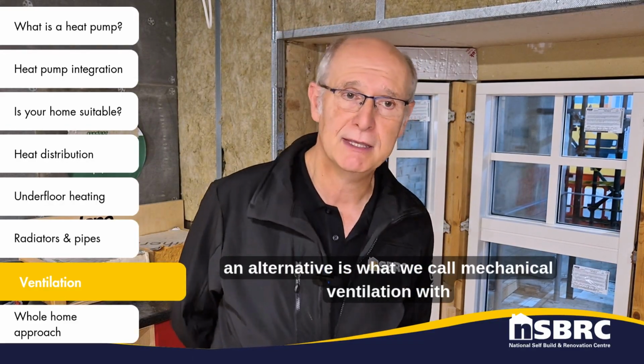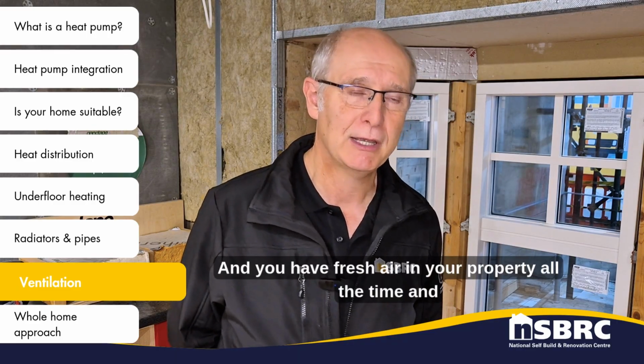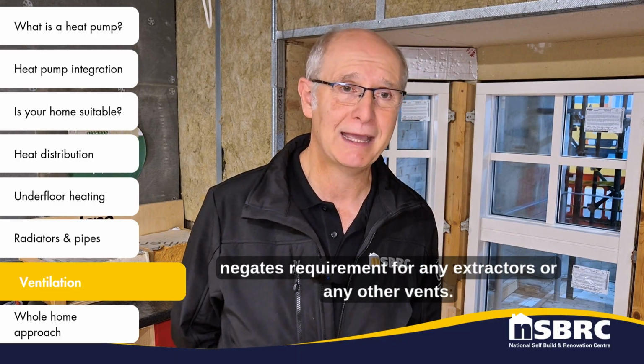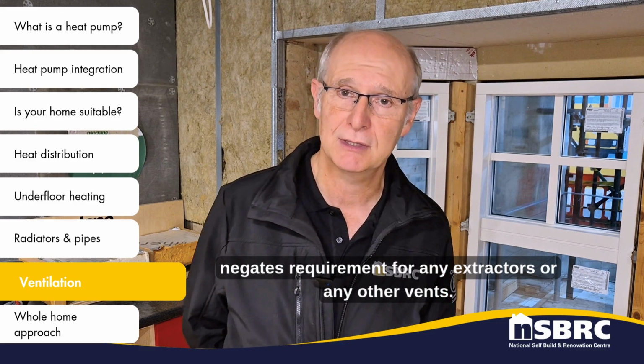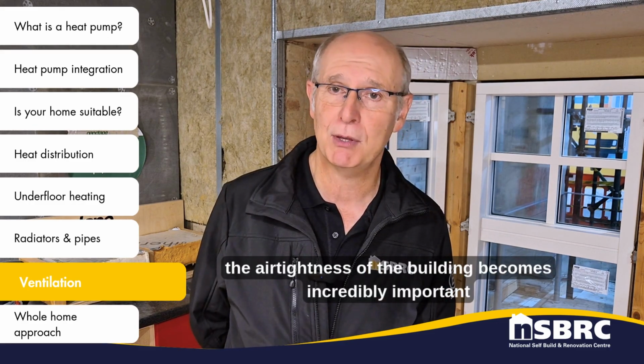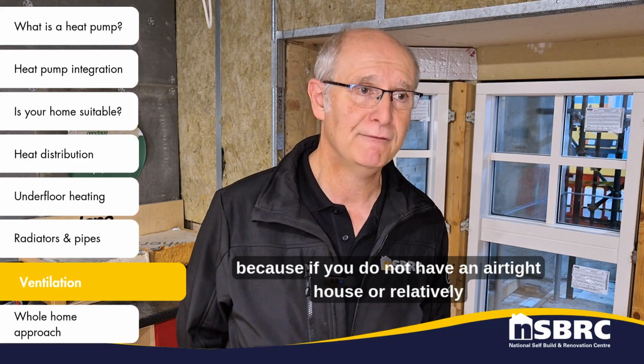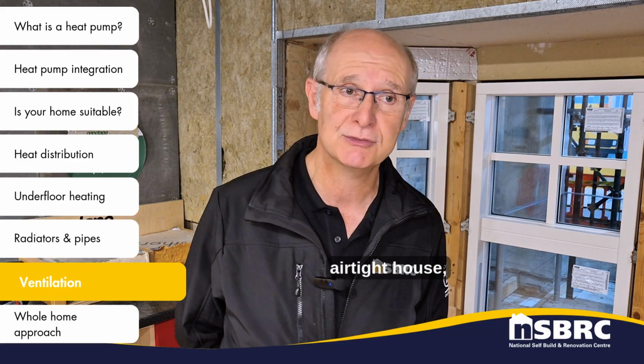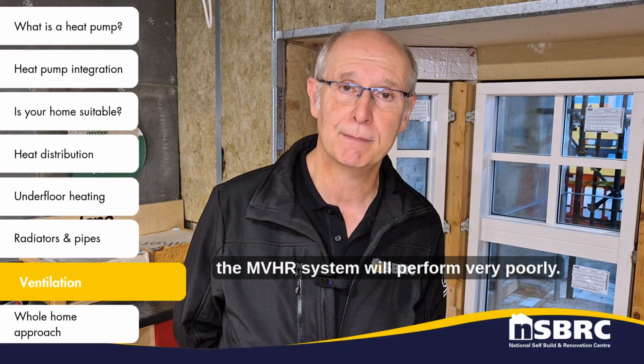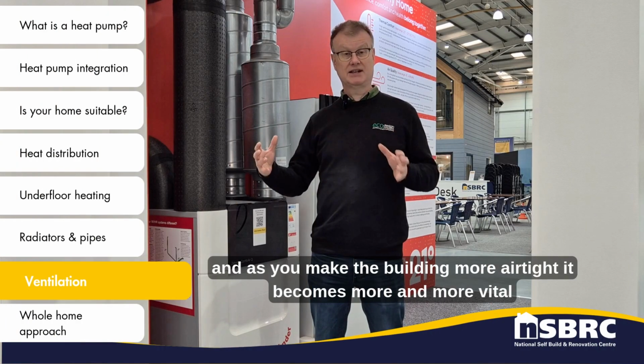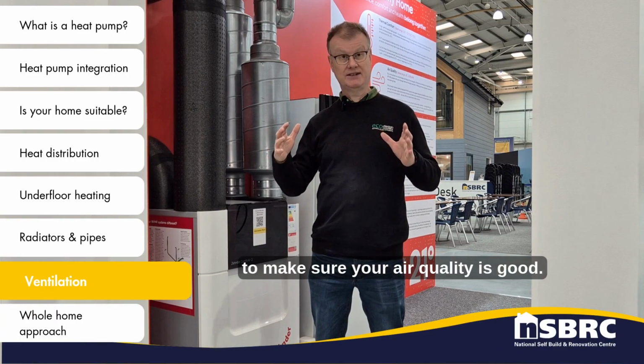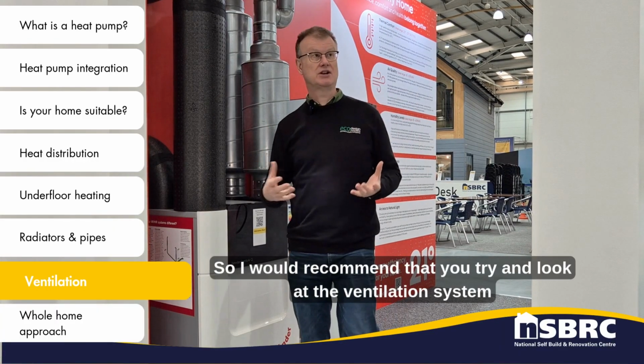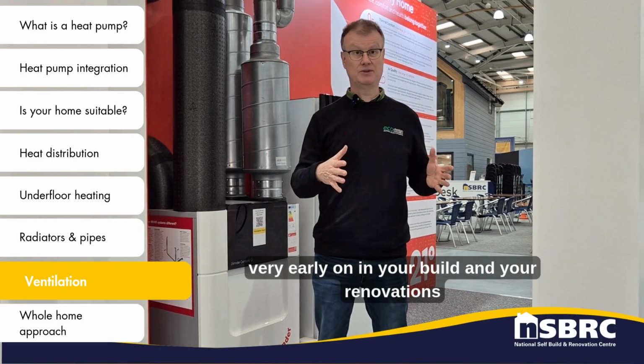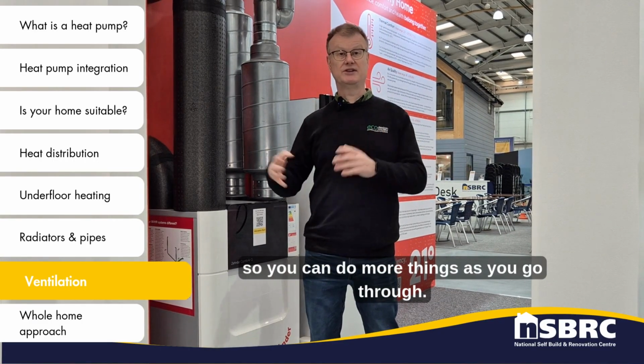Now, an alternative is what we call mechanical ventilation with heat recovery. This is a whole house system which naturally ventilates your property beautifully, and you have fresh air in your property all the time and negates the requirement for any extractors or any other vents. But if you are going down this route, the air tightness of the building becomes incredibly important, because if you do not have an airtight house, or relatively airtight house, the MVHR system will perform very poorly. And as you make the building more airtight, it becomes more and more vital to make sure your air quality is good. So I would recommend that you try and look at the ventilation system very early on in your build and your renovations, so you can do more things as you go through.